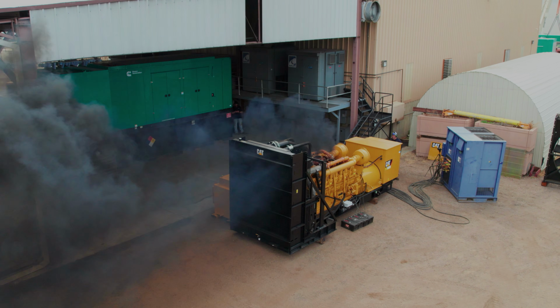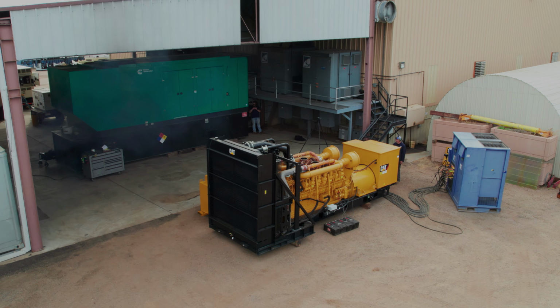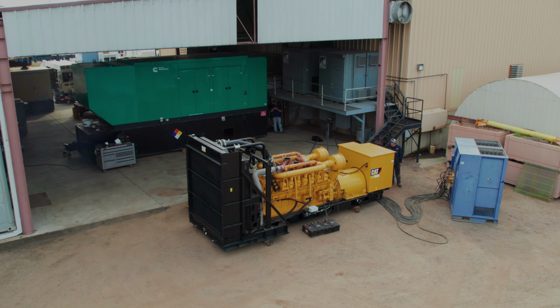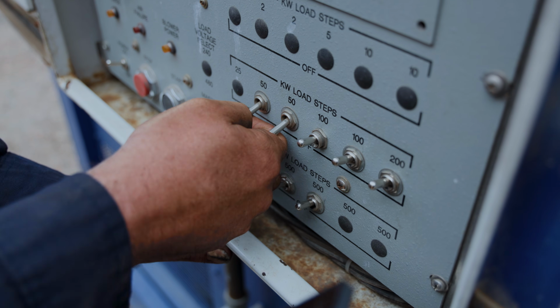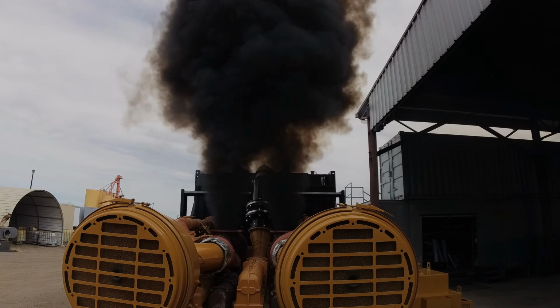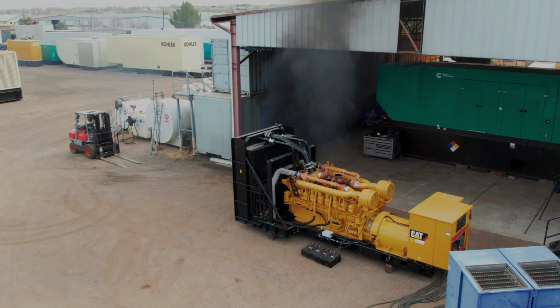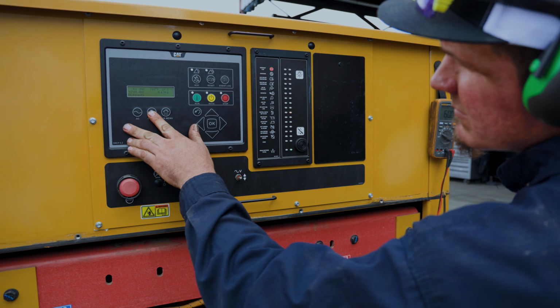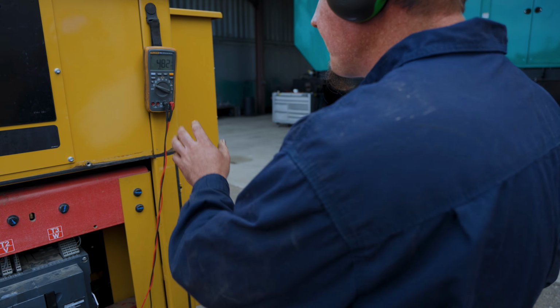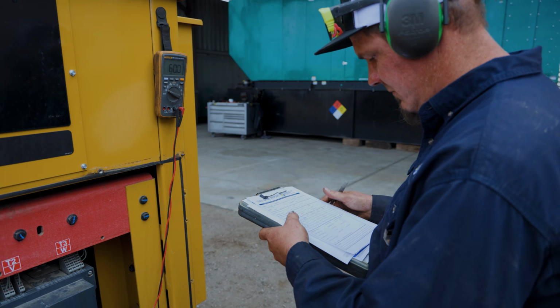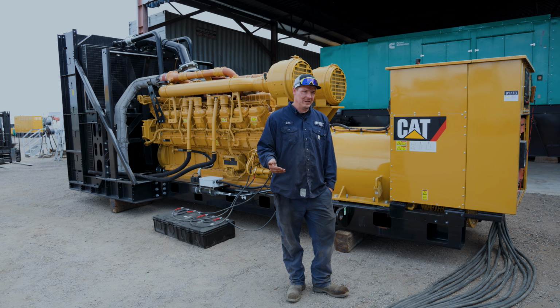So you're going to run it at 25 or 30% for 10-15 minutes, then you're going to step it up to 50%, and then 80% you're going to do it 30 minutes to an hour. We're going to record pressures, temperatures. We're going to make sure that it is putting out the correct voltage and that it is stable.